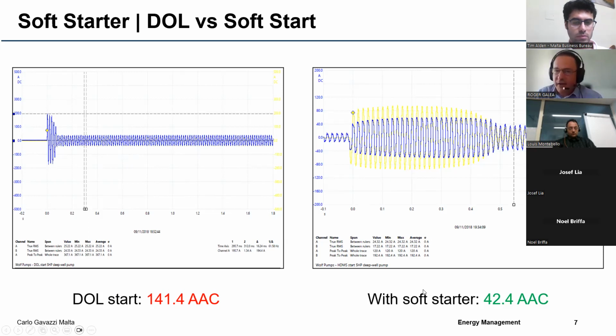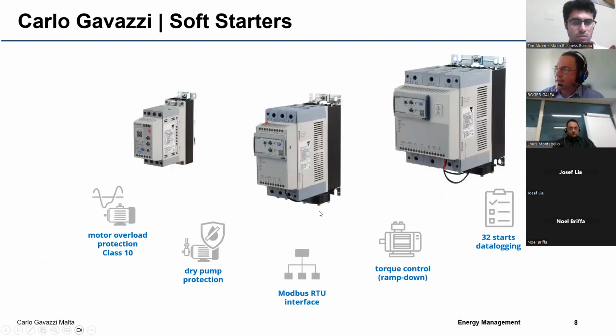So with a soft starter, we managed to obtain a reduction of 70% in the initial current. As you see, this is the nominal current of the motor, and this is the initial current. This is something that we deployed in our own equipment. So Carlo Gavazzi has a wide range of soft starters now, which are very much conversant with the new high efficiency motors, and can be deployed in such environments for higher efficiency solutions.